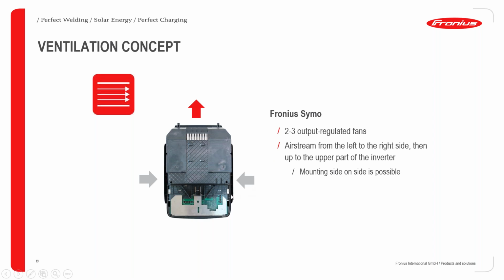So we have fans situated below and above the inverter. What happens is that the cold air is sucked in from below, as you can see from the sides. These fans can be either 2 or 3, depending on the capacity or size of the inverter. But basically, cold air is sucked in from the side below the inverter, and then hot air is let out from the top. By so doing, you have a well-regulated airstream that flows from the side to the upper part of the inverter.